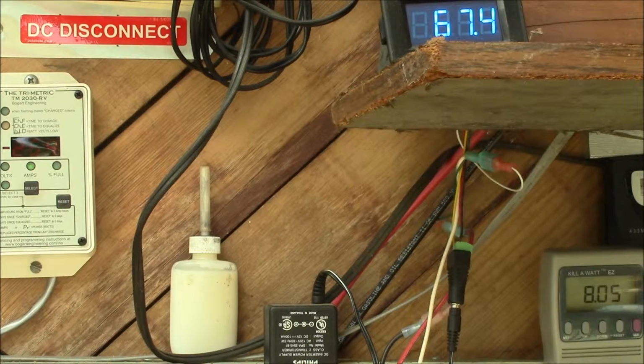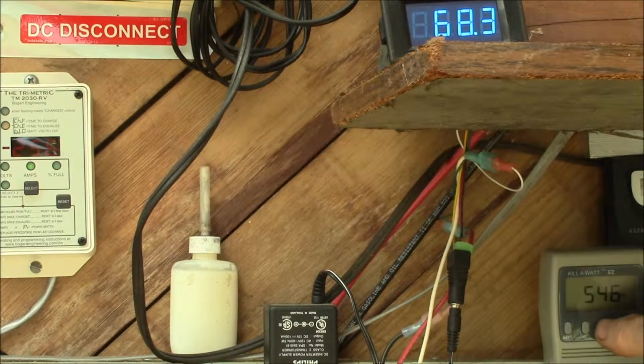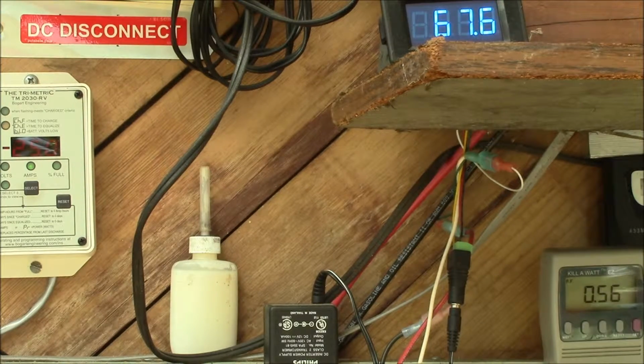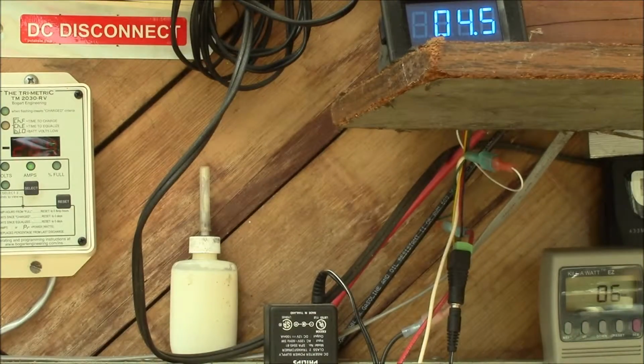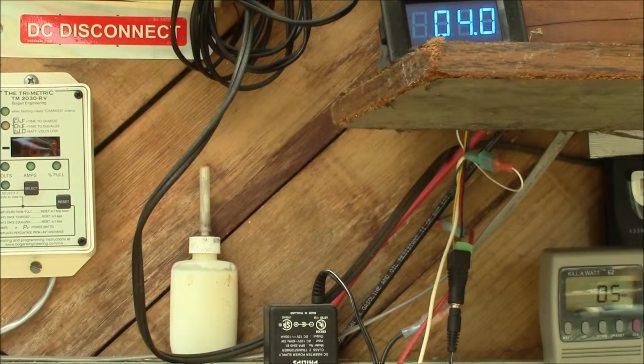And again, if I pull the power factor capacitor out of there, that jumps up to 9.3. What else do we have? 546 watts, 970 volt amps, and 0.56 power factor. You can see now it's shut down. Might try to calculate the proper size run capacitor to correct the power factor on this, and then just see if I can get in the washer and wire it in parallel with the motor. And in fact, I think I'd probably need more than 30 microfarads, so I'll run the numbers on this and see what kind of run capacitor that particular motor would need.